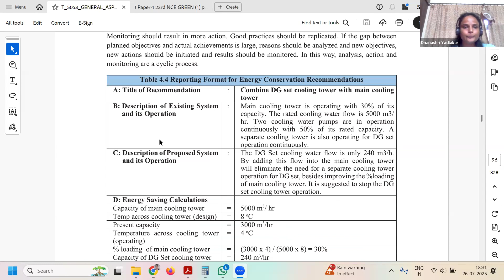So the title of recommendation: combine DG set cooling tower with main cooling tower. The description of the existing system, what they have in operation. The main cooling tower is operating at 30% of its capacity. The rated cooling water flow is 5,000 meter cube per hour. Two cooling water pumps are in operation continuously.